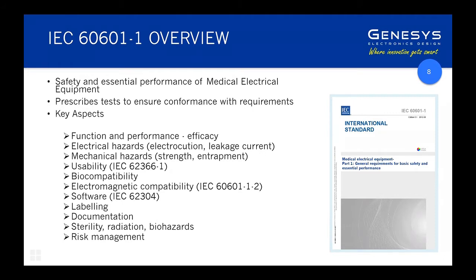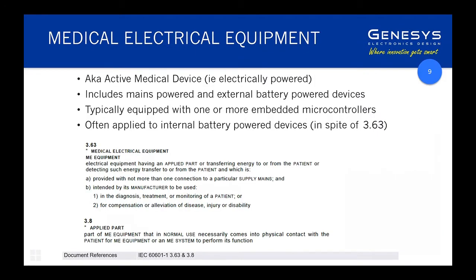Medical electrical equipment as defined in 60601-1 does not technically include battery-powered devices with no mains connection. However, this standard is broadly applied to battery-powered devices in practice — the regulators will expect you to have applied it even though strictly speaking, under Clause 3.63, they're out of scope. I think that's an indication the standard has gotten a little out of date in terms of the way electrical equipment in the medical space is going.